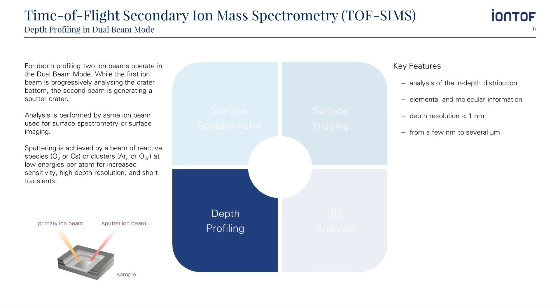For depth profiling, two ion beams operate in the dual beam mode. While the first ion beam progressively analyzes the crater bottom, the second beam generates a sputter crater. Sputtering is achieved by a beam of reactive species — oxygen or cesium — or clusters at low energies per atom for increased sensitivity, high depth resolution, and short transient. Key features include analysis of the in-depth distribution of elements and molecules, a depth resolution of around one nanometer, and the ability to analyze samples from a few nanometers to several microns in depth.